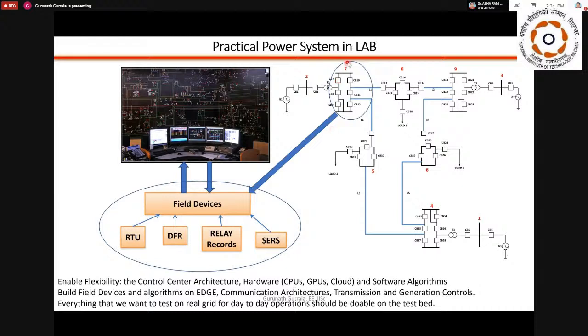So what do I mean by substation configurations? For example, to connect three particular lines, one transformer and two lines on the downside, the substation uses what's called a breaker-and-a-half scheme, which is widely used in all 400 kV substations in India. There's also the ring bus scheme, used when high reliability is required, especially for supplying power from different feeders to a city. There are other configurations too, which I'll explain in the next slides.